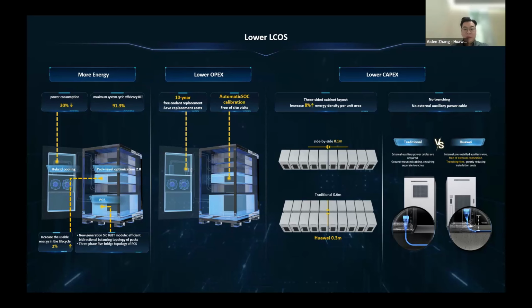In terms of design, side by side, the clearance required is only 0.1 meter. Traditionally, front to back, the setback distance should be about 0.6, but for our C&I ESS, the required setback distance is only 0.3 meters. So that's, on the cost or dollar sense, also one of the considerations when you are selecting a BESS system to add on to your PV or as a standalone system.